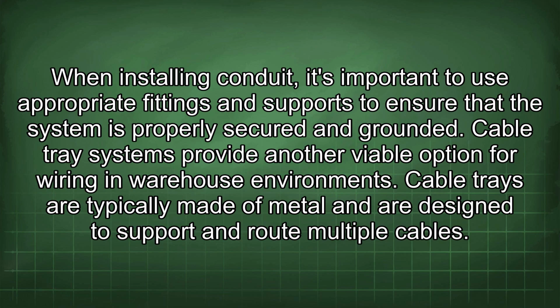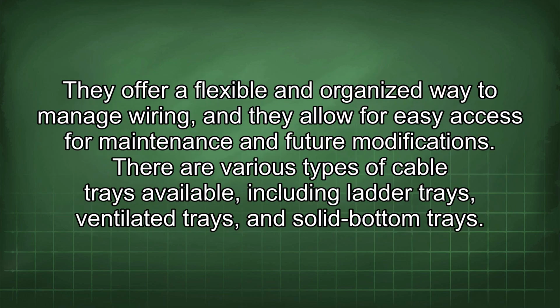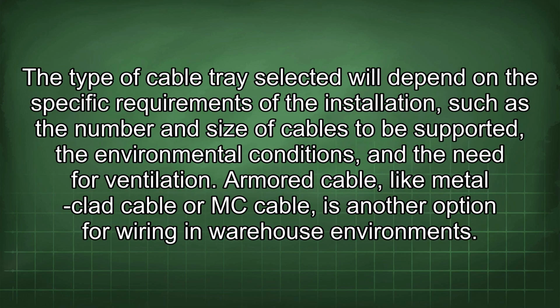Cable tray systems provide another viable option for wiring in warehouse environments. Cable trays are typically made of metal and are designed to support and route multiple cables. They offer a flexible and organized way to manage wiring, and they allow for easy access for maintenance and future modifications. There are various types of cable trays available, including ladder trays, ventilated trays, and solid bottom trays. The type of cable tray selected will depend on the specific requirements of the installation, such as the number and size of cables to be supported, the environmental conditions, and the need for ventilation.